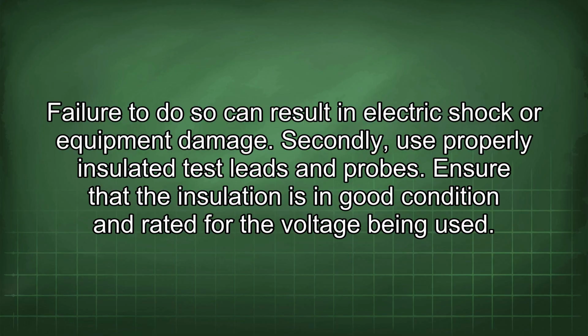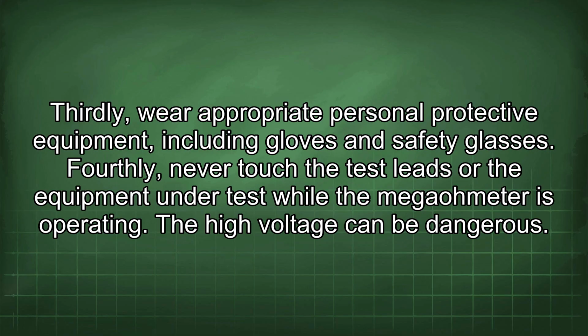Ensure that the insulation is in good condition and rated for the voltage being used. Thirdly, wear appropriate personal protective equipment, including gloves and safety glasses. Fourthly, never touch the test leads or the equipment under test while the Megohmmeter is operating. The high voltage can be dangerous.